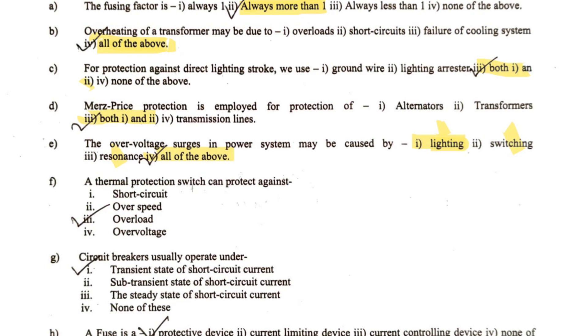The next question: a thermal protection switch can protect against — short circuit, over speed, overload, or over voltage? A thermal protection switch operates when the current flowing is above the rated current but not as abnormally high as a short circuit current. So it can provide protection for overload, but not for short circuit or any other kind of fault. Option three — overload — is the correct answer.